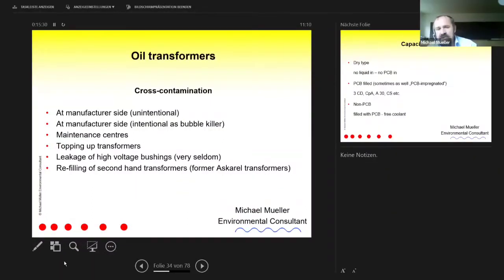So they took the Askarel tank, the pump system, and they filled the Askarel into the transformer. The next transformer comes to the filling station, and the utility sector, distribution sector, says, Askarel, too expensive, we don't need it, we take oil. Now they switch to the oil tank, and now the oil goes through the same pump system, but in the pump system we still have half a liter or 1 liter of Askarel, and that goes with the oil into the oil transformer. And this transformer is now highly contaminated.